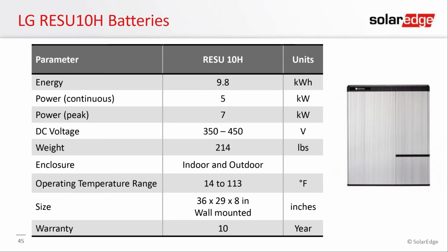The Resu10H is actually a 9.8 kilowatt hour battery bank, and it has a depth of discharge of 95%, meaning the usable energy is 9.3 kilowatt hours. Its continuous discharge is 5 kilowatts, which matches what StorEdge does, but the peak discharge is 7 kilowatts. So we're going to be limited by the inverter in this standpoint, so we're still limited to 6.6 kilowatts.